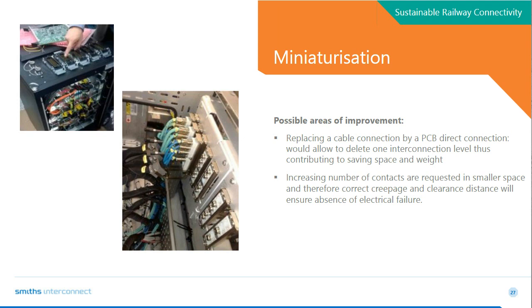One very interesting option is to replace cable interconnection with a direct connection on PCBs, printed circuit boards. The main challenge I see with direct connection on PCB, Alain, is that we have to keep very high robustness, and we need to keep a blind mating function, especially when electrical racks are mated in electrical cabinets. Managing PCB connector interconnection properly is key to managing the miniaturization I mentioned before.